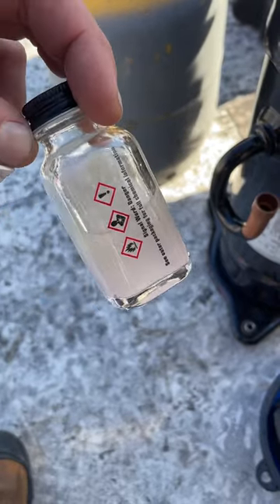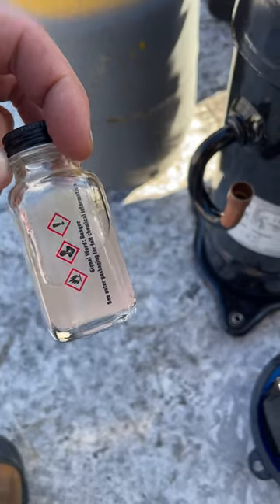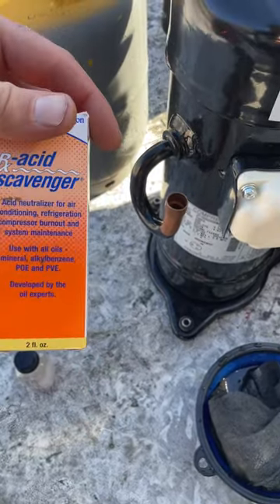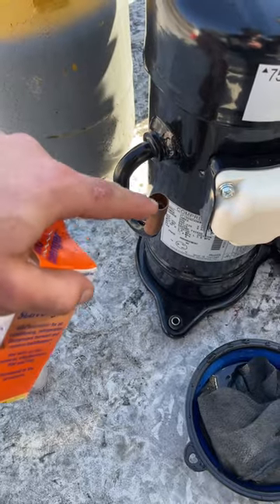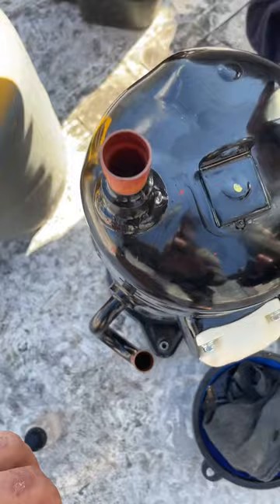The system tested positive for acid. I really prefer the oil test over the refrigerant test. Now, you can get your acid scavenger in there by pouring it in, but it's especially difficult on these Daikins because of this oil trap.